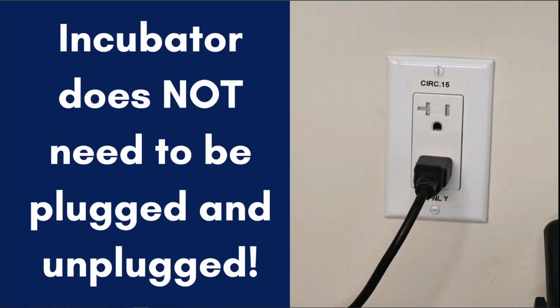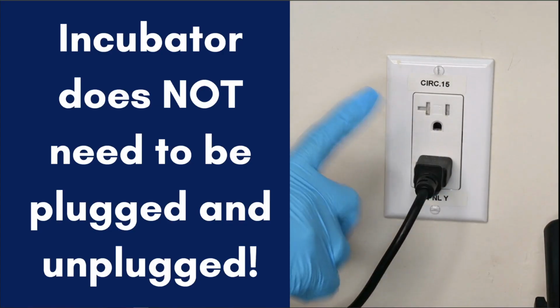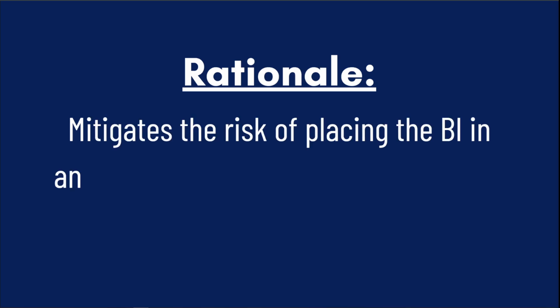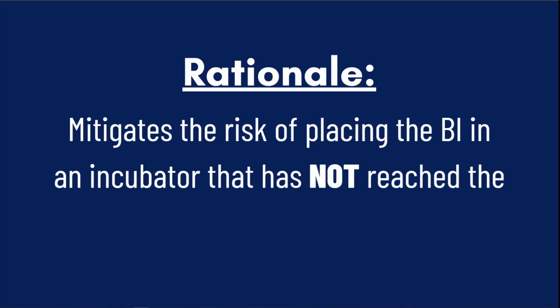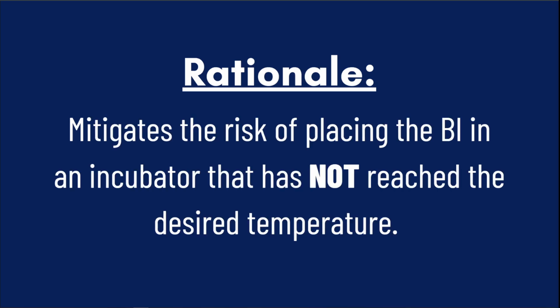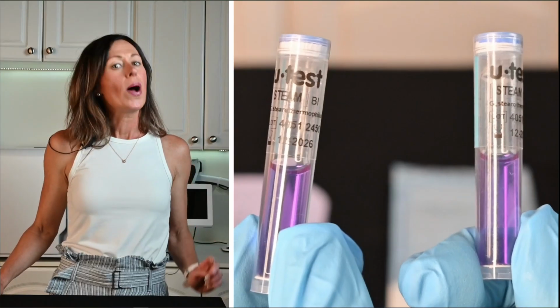Ensure the incubator is plugged into an electrical outlet and has had time to reach the required temperature of 60 degrees Celsius. The incubator does not need to be plugged and unplugged at each use. The rationale is this mitigates the risk of placing the BI in an incubator that has not reached the desired temperature.